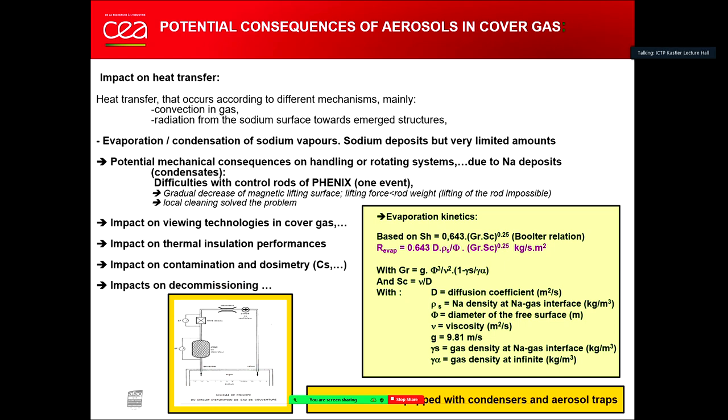On Superphénix, we made some very funny study. There were some questions about the aerosols. We developed a system, not in the primary vessel, but in the external vessel for storage of the fuel assemblies, in order to characterize these aerosols and their coming back into the sodium. We developed through the slab a fishing technique, I would say, to go to the surface and sample the aerosols which are deposited on the sodium surface, extract them, and send them to the laboratories, thanks to the tight system. One expert was with a visualization means, and the other one was moving the fishing rod. And I was participating in this fishing party in Superphénix.